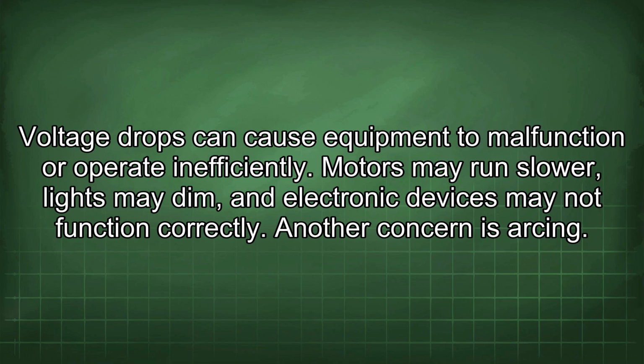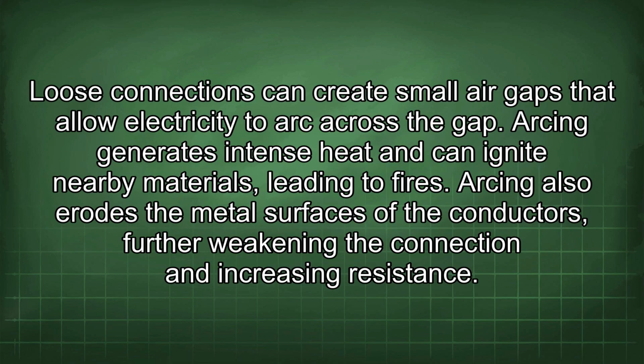Another concern is arcing. Loose connections can create small air gaps that allow electricity to arc across the gap. Arcing generates intense heat and can ignite nearby materials, leading to fires. Arcing also erodes the metal surfaces of the conductors, further weakening the connection and increasing resistance.